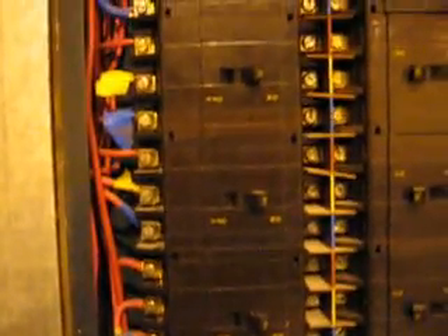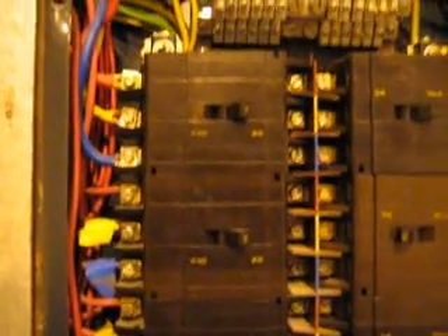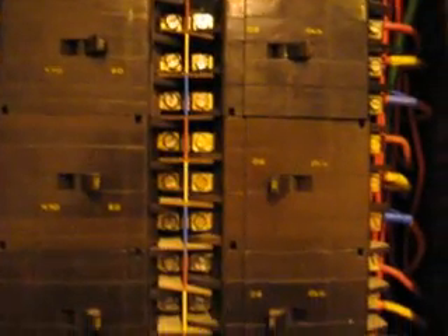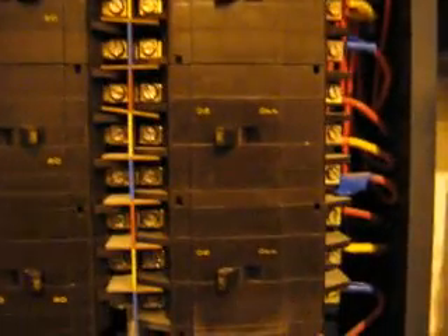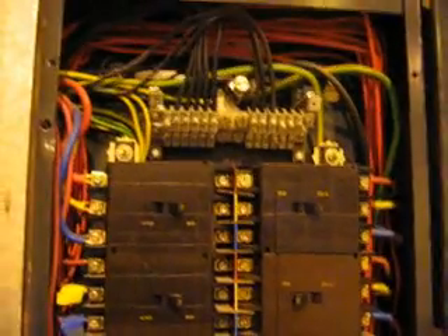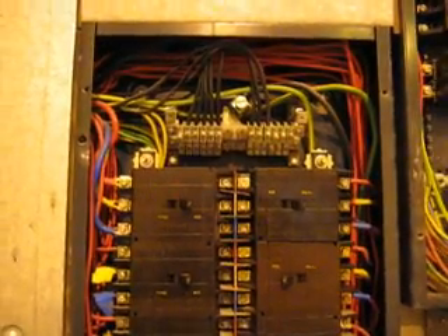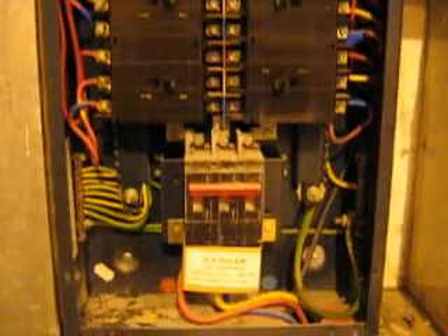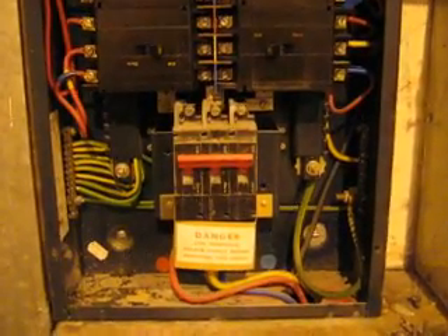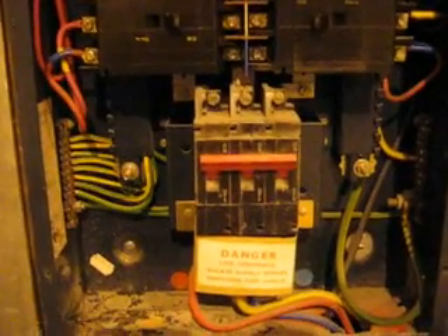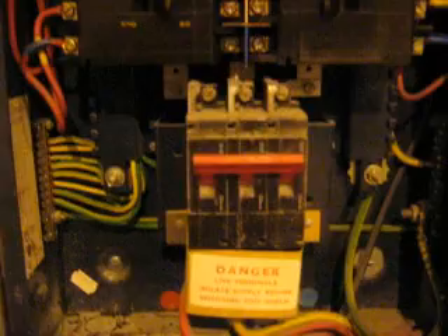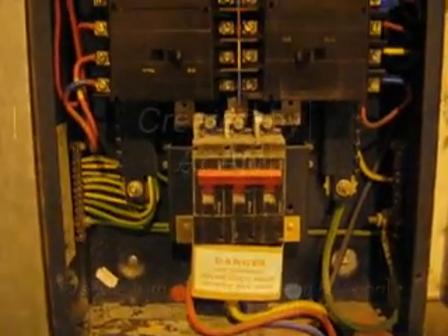This distribution board is fitted with Crabtree C50 circuit breakers. These circuit breakers are of an obsolete pattern. They are at least 20 years old, maybe older. The circuit breaker physical size is larger than that of the current range, and these circuit breakers work on a principle called magnetic hydraulic. They produce a time delay without the resistive thermo metal that you've got in the current range of BS 60898 or 3871 circuit breakers. This is the main switch, and this is live at 415 volts.